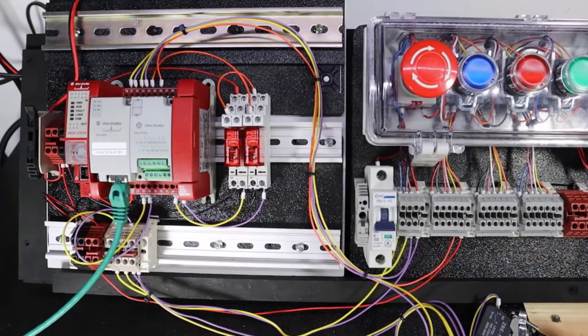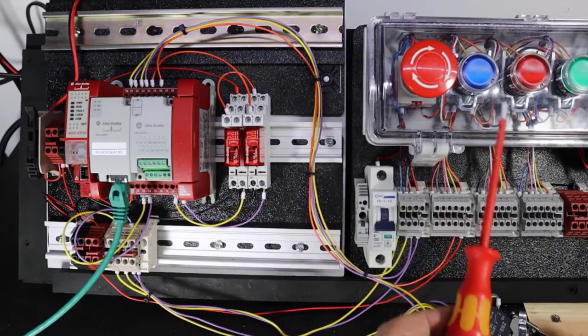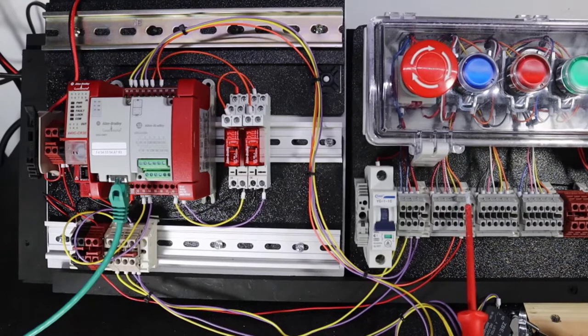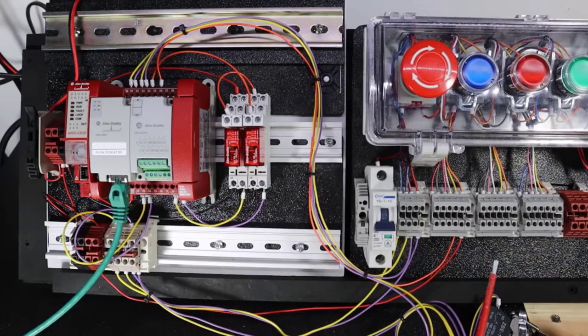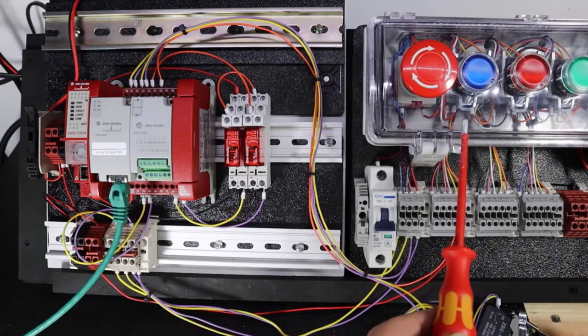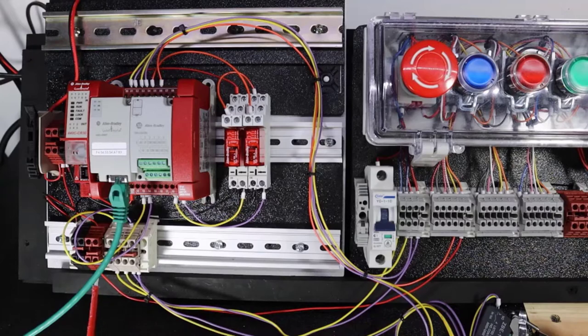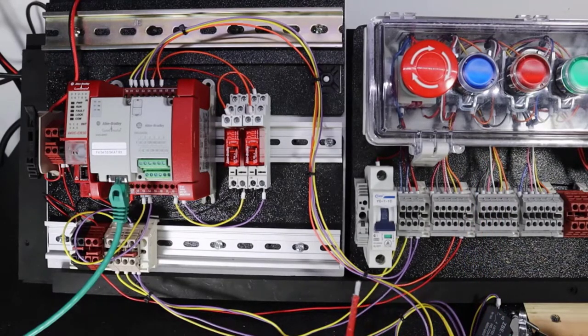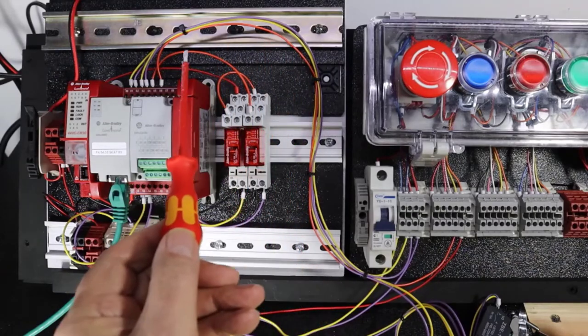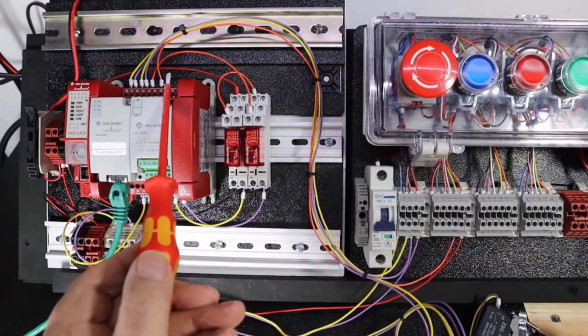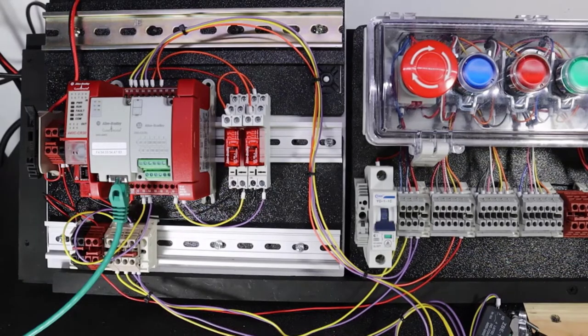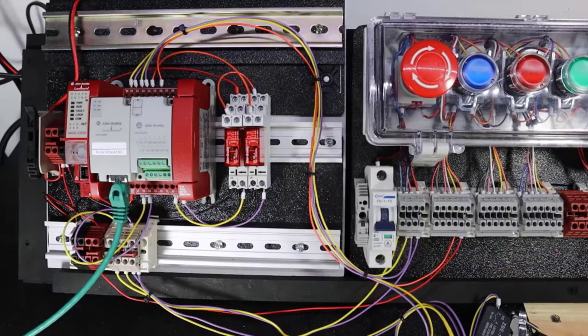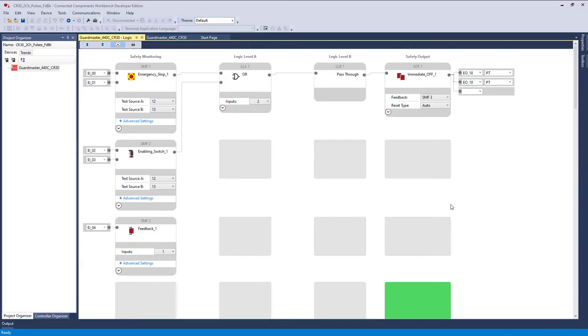For our reset button, we're using this blue button right here. We're using the orange and yellow wires coming off of that contact block, and we're feeding this switch with that red wire going directly from positive to the switch, then coming out of the switch through the orange wire and over to the next available safety input, which is input number 5. So that's really all that we have. I know it's starting to get congested, trying to keep it as neat as we can.